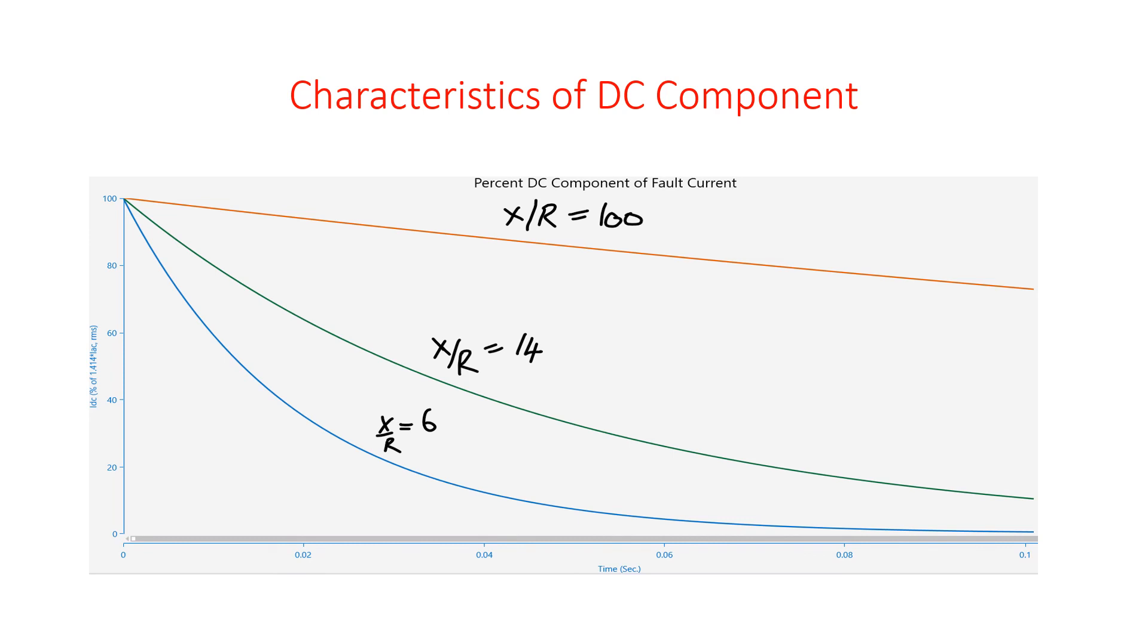This is how the peak value is different in the case of previous ETAP model. X by R value deciding the DC component decay, which in turn decides the peak current of fault current. I hope you can understand what is the importance of X by R ratio in the power system.